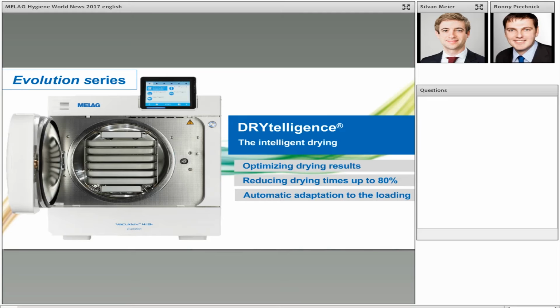Drying time consumes up to 20 to 30% of the whole sterilization process. So drying is quite a bit when it comes to energy efficiency. And this is why our in-house engineers have developed an algorithm that allows adaptable drying according to the amount of instruments on the one hand and the type of packaging on the other hand. So with this new Dry-Telligence, we have an intelligent, fully automatic, adaptable drying technology that allows reducing drying times of up to 80%. Of course, that depends on the actual loading that is in the autoclave.